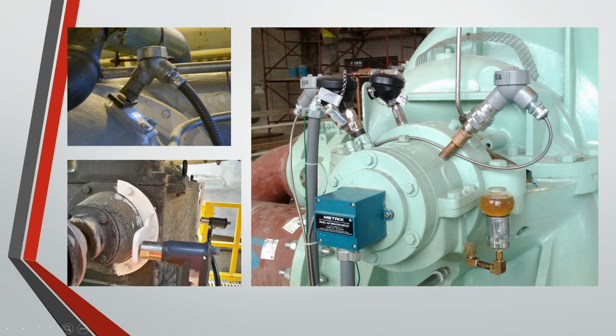But something you want to be really careful of is this picture down here. You can see that in order to get the same velocity sensor mounted on the machine surface, the customer created a half or semicircle portion of a flange and then welded this cantilever beam out there. In terms of position, the sensor is near where it needs to be, but it's not actually on that surface. So if there's vibration happening in this housing, it has to transfer through the flange and then into this cantilever beam. We're potentially losing some vibration in the flange, and then this cantilever beam is filtering the vibration with its natural frequency, because it's going to have its own natural frequency that it's vibrating at.